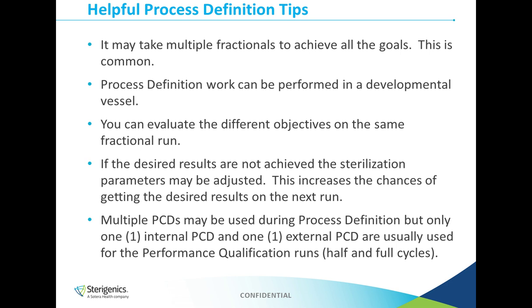Now you can also include product sterility, but traditionally, that product sterility isn't placed on a fractional run until you have a better idea of what gas dwell time is going to give you fractional growth. If you're starting from scratch and this is your first validation with this product, you may not know at what gas dwell time is going to give you fractional growth. So for fractional 1 and maybe 2, you're trying to find that optimal gas dwell time to give you that quantitative growth on the BIs. And then once you achieve that, on the next fractional run, you can go ahead and include product sterility samples. And that's because now you're more confident that that run is going to give you the results on the internal PCD so that you can compare it back to the product sterility.